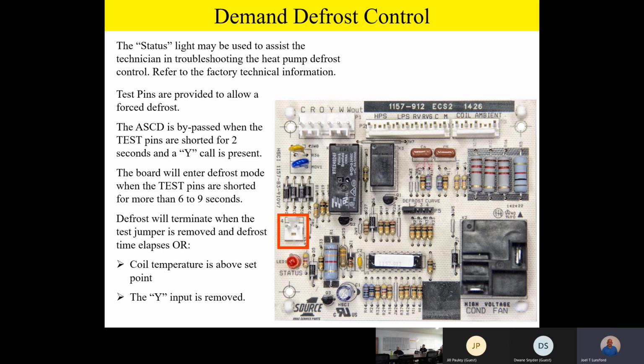So just remember, if you get on a job and you force a defrost and it jumps right out of defrost, but you still want to clear the coil, you're going to have to hold that jumper on there until the coil's clean. So that's kind of a nice little thing you can do. You can actually manually defrost the coil, and you can sit here and watch it and make sure all the ice gets off. If you jumper those pins and you hold the jumper on there, it ignores the sensors as long as those pins are jumpered. Now remember, defrost termination is going to take place when the coil temperature is above set point, or if you remove the Y input, it'll also terminate the defrost.